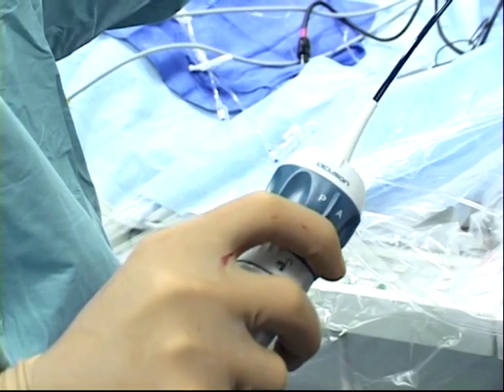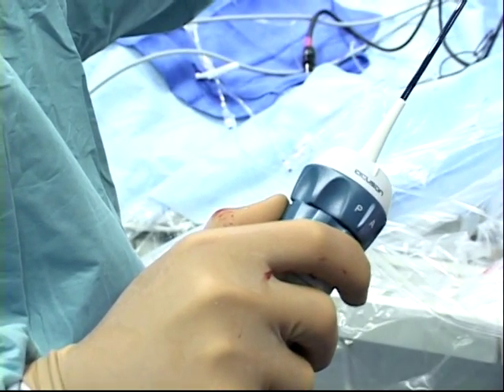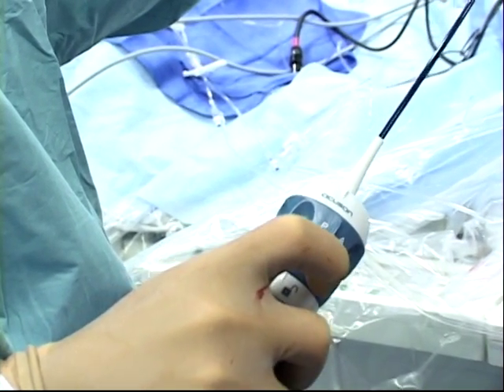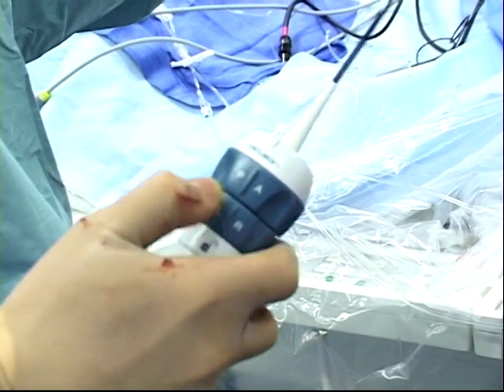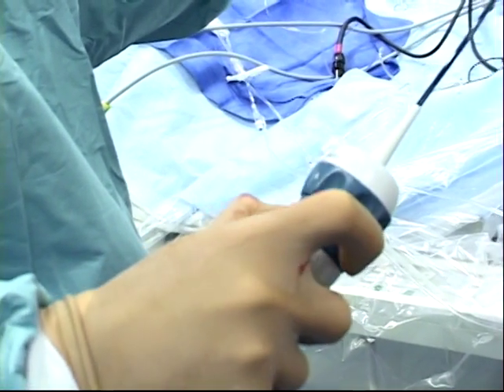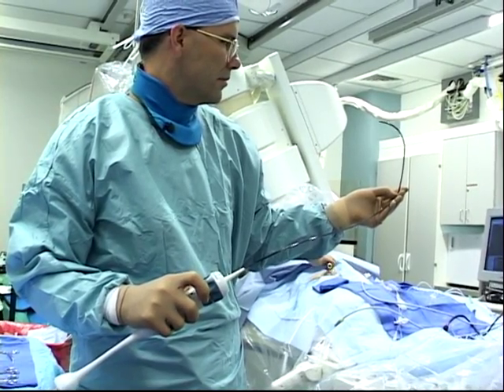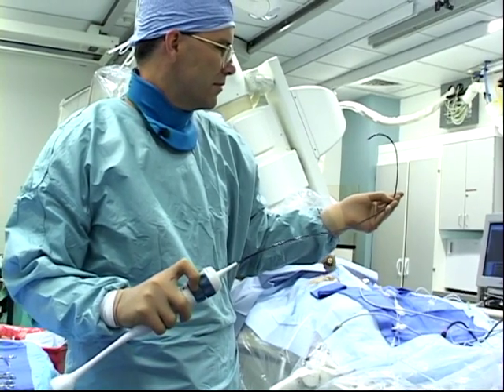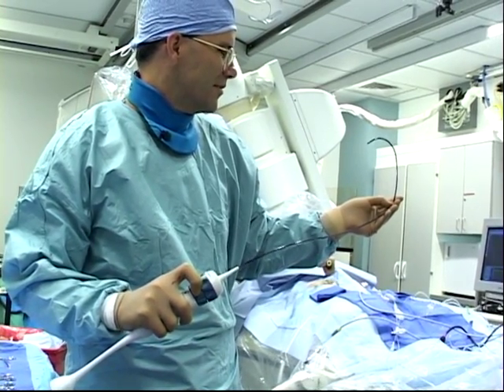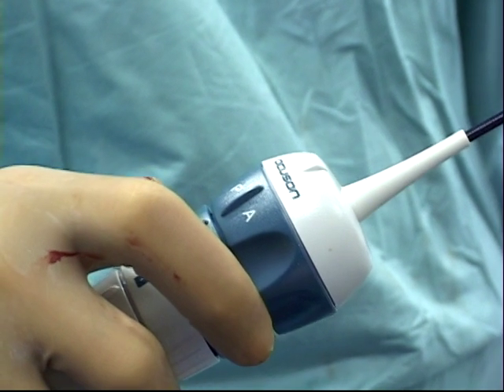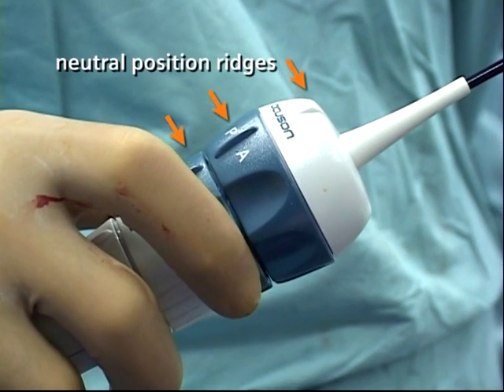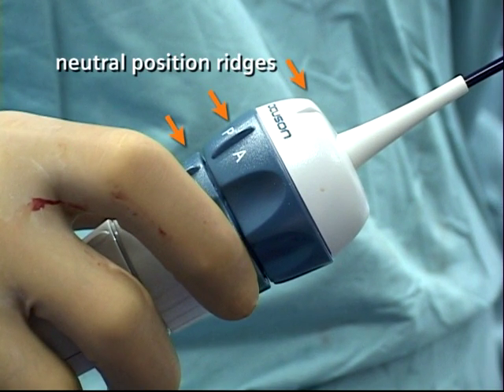Now turn the left-right steering knob clockwise to steer the catheter tip to the right, and then turn it counterclockwise to steer it to the left. The knobs should move freely without binding, and the catheter tip should flex in the direction toward which the knob was steered. To straighten the tip of the catheter, turn the steering knobs so that the neutral position ridges are aligned.